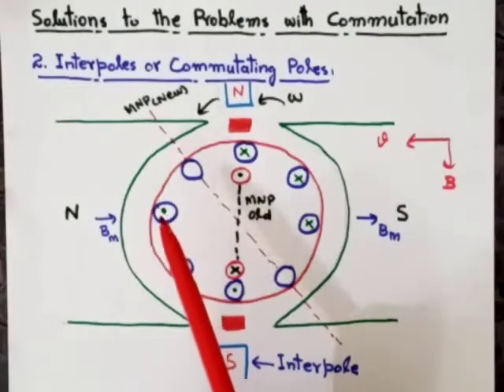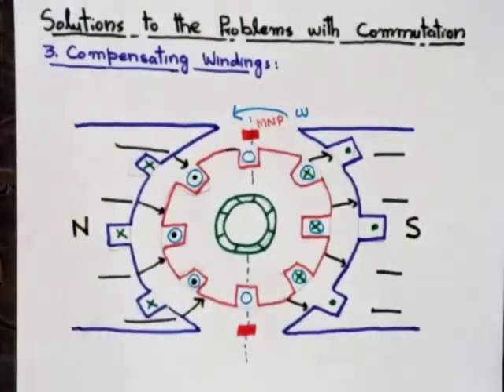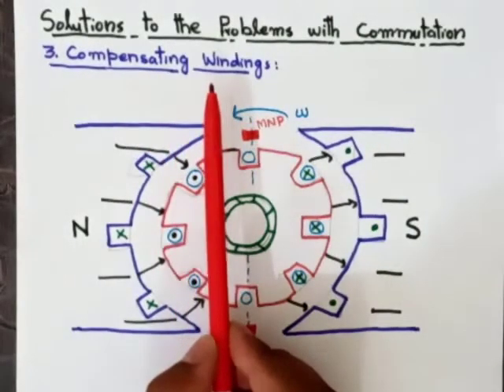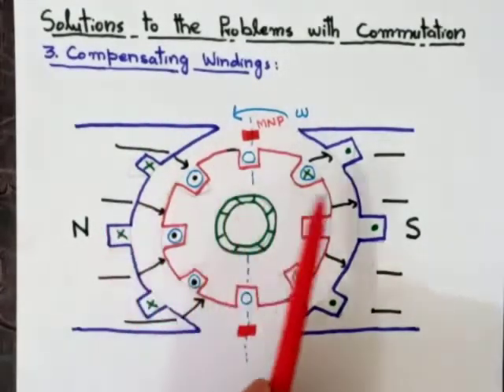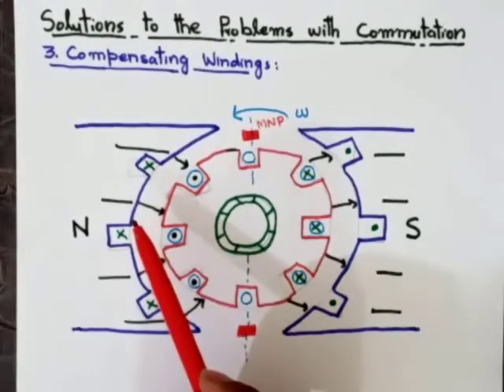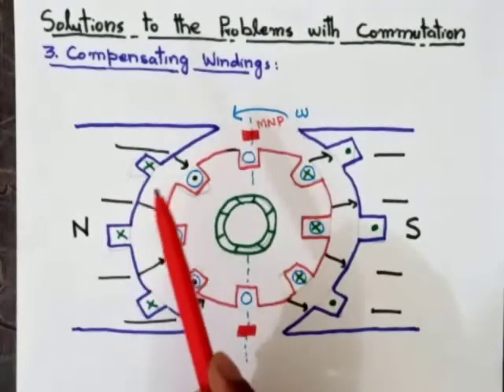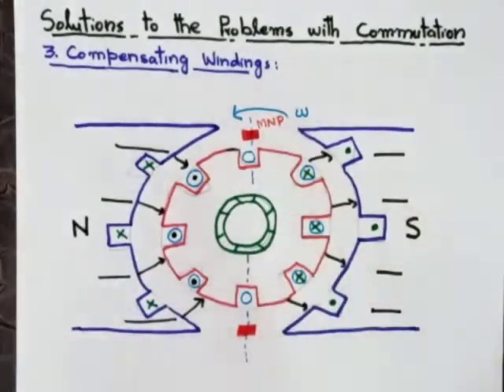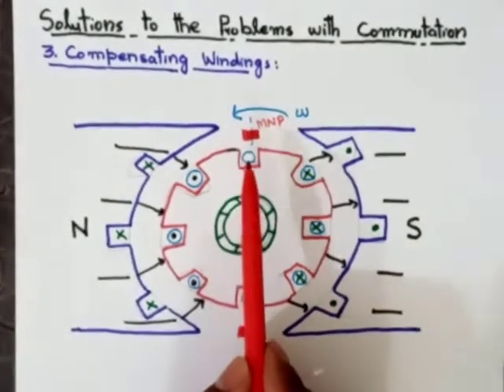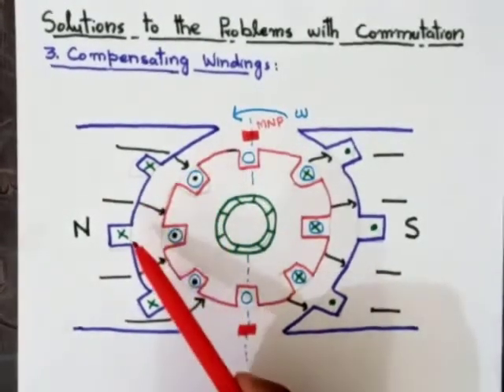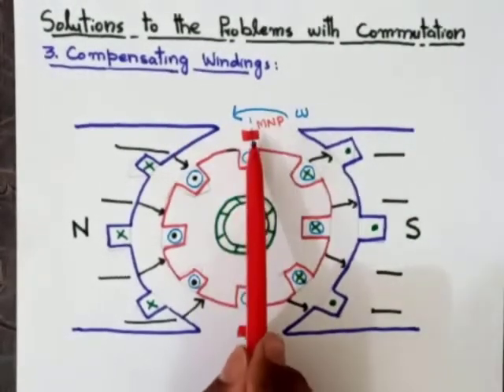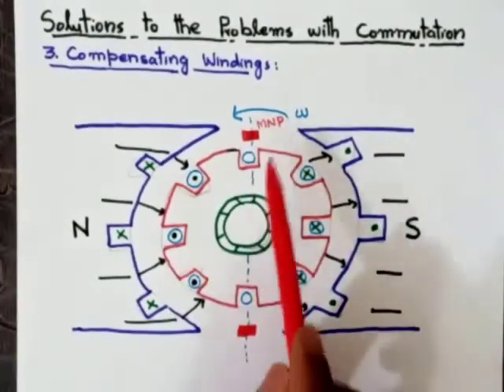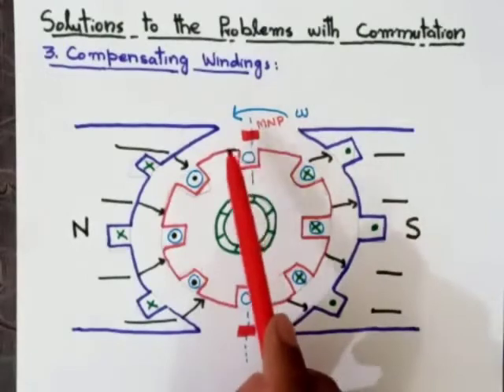The third method to improve the commutation is compensating windings. This technique will help reduce the flux weakening problem, which exists under the north and south poles. Remember, this particular technique will not help overcome the L·di/dt voltages — for that, you will still use interpoles. This technique only helps minimize the effect of flux weakening. It will also not minimize sparking across the brushes directly — for that we use interpoles.